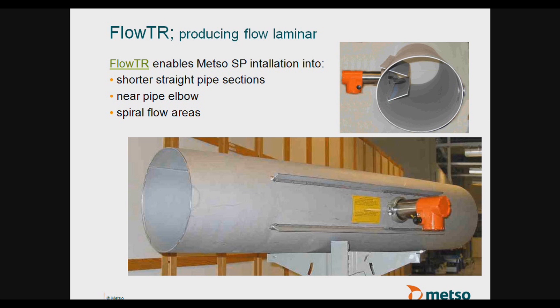Now what happens if we do not have enough straight pipe requirements? Metso offers a FlowTR turbulence reducing vane. Metso's FlowTR vanes can be installed in an existing pipe or we can supply the spool sections here. Typically these vanes are about 36 inches long. If you don't have enough straight pipe requirements with just the pipe, these vanes allow you to get laminar flow without the required straight pipe.